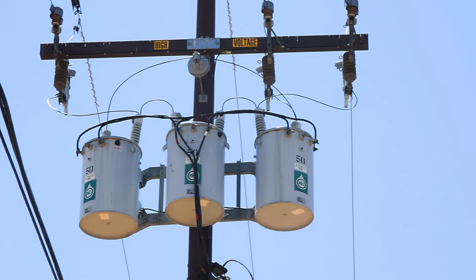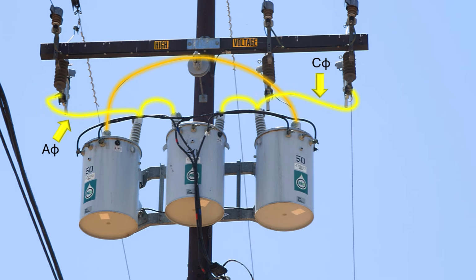You can also see this type of connection here. The jumper wire connecting the two transformers on the left, the jumper connecting the transformers on the right, and the long jumper connecting the two outer transformers. The A-phase lead wire is shown here, along with the C-phase lead wire, and lastly, the B-phase lead wire.